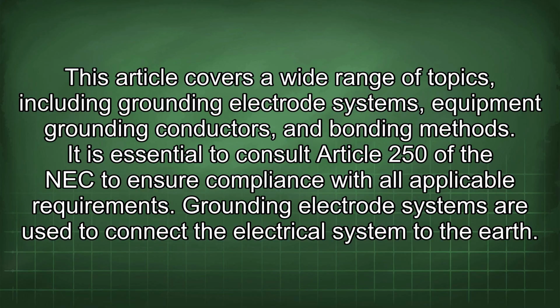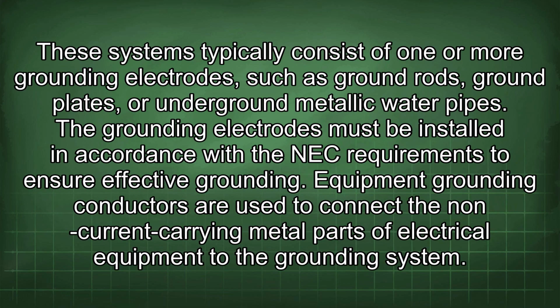Grounding electrode systems are used to connect the electrical system to the earth. These systems typically consist of one or more grounding electrodes, such as ground rods, ground plates, or underground metallic water pipes. The grounding electrodes must be installed in accordance with the NEC requirements to ensure effective grounding.